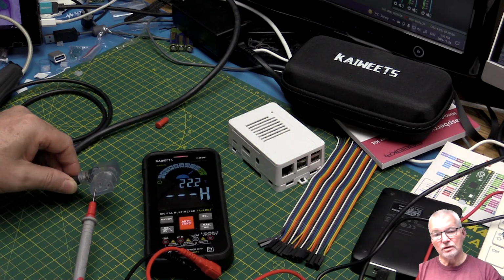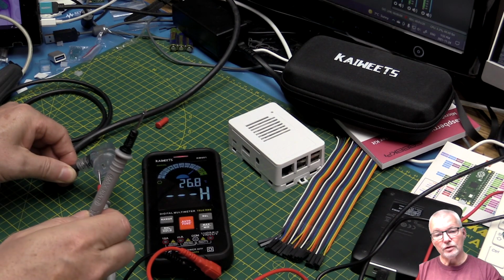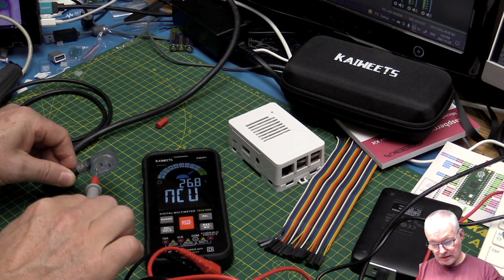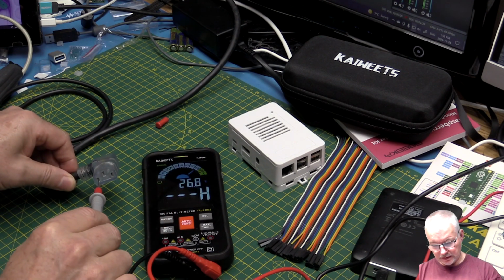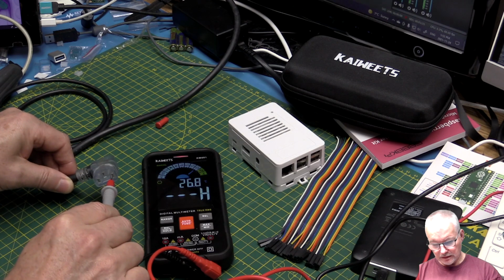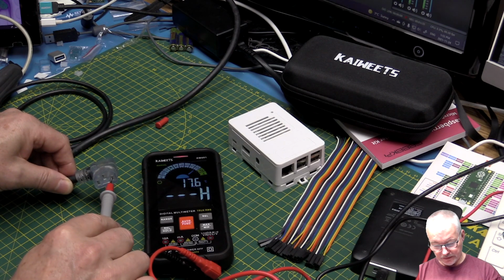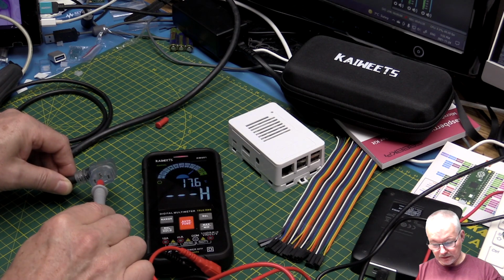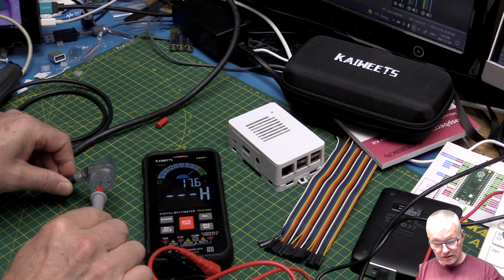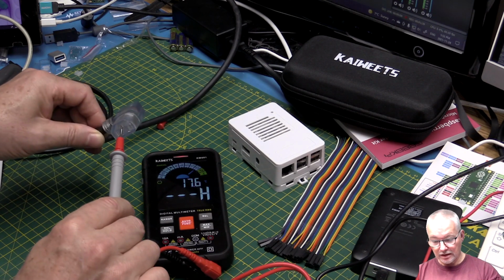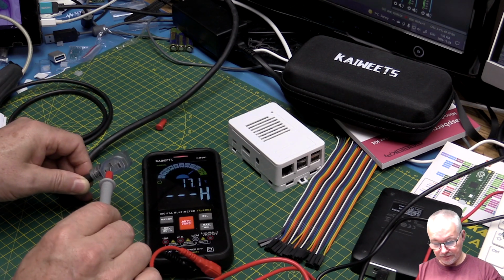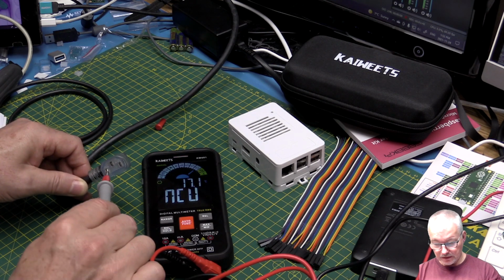So okay, now does it work with obviously sticking a single probe in? You don't have to put both in. So that's live. That shows high as well, and that's the ground lead. So either way, since this is plugged into mains, it's still sensing the high voltage on any one of those.